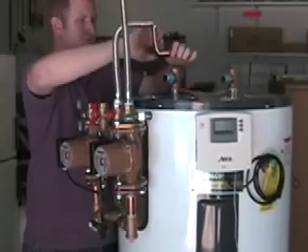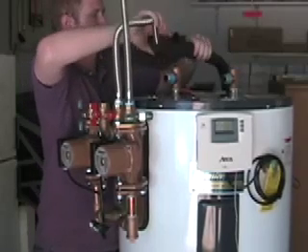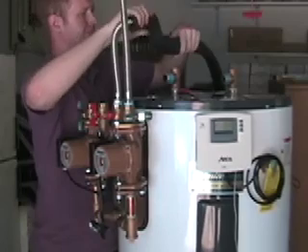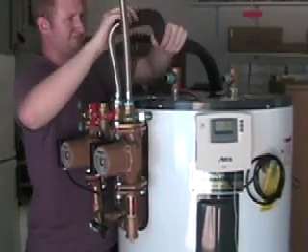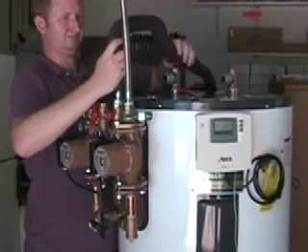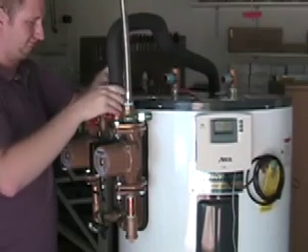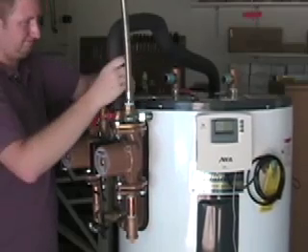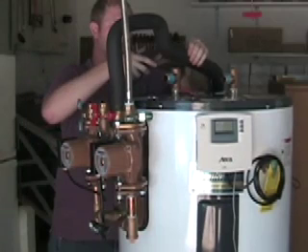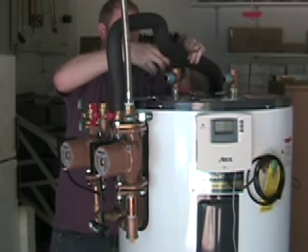Once you've bent the stainless steel line roughly in place, you're applying half inch elastomeric insulation. These are three quarter inch nominal stainless steel lines with a half inch Rubatex elastomeric jacket on the outside. This is not polyethylene — it is a higher temperature, higher quality insulation. It is sold at Lowe's but is primarily used in HVAC trades. By using non-slit Rubatex you accomplish the insulation faster and with a higher quality fit, without seams that need to be taped or glued later.